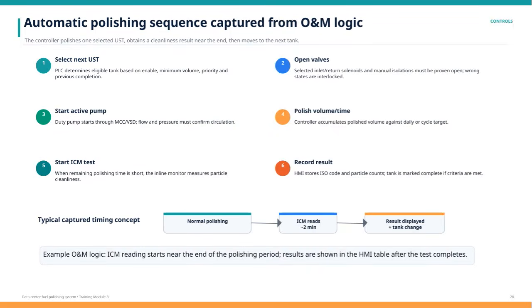Here, we see the automatic polishing sequence as captured from the operation and maintenance logic. The process starts with the controller selecting one underground storage tank, or UST, to polish. Near the end of polishing, the system obtains a cleanliness result before moving to the next tank. Let's break down the controls involved. First, the PLC selects the next eligible tank by evaluating factors like whether the tank is enabled, its minimum fuel volume, its priority status, and whether it has been recently completed.